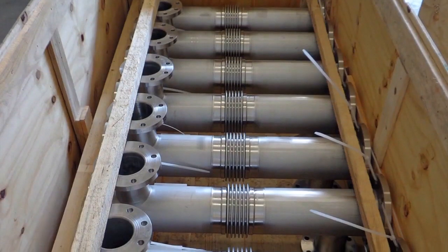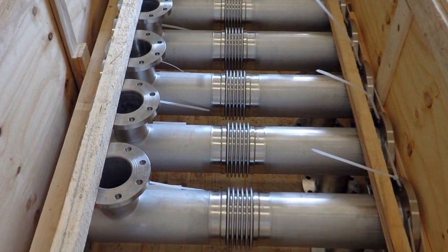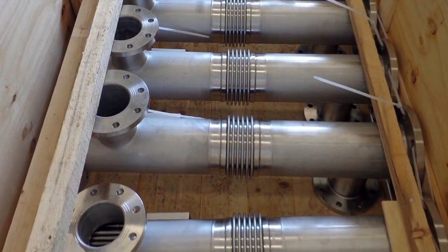The most traditional application involves tubular bundle heat exchangers with double tubes, double walls, which have the particularity of having heads built in such a way that if there is a leak, this leak ends up in a chamber between the two heads. Consequently, it is possible to verify that there is a leak, intervene, repair, etc.